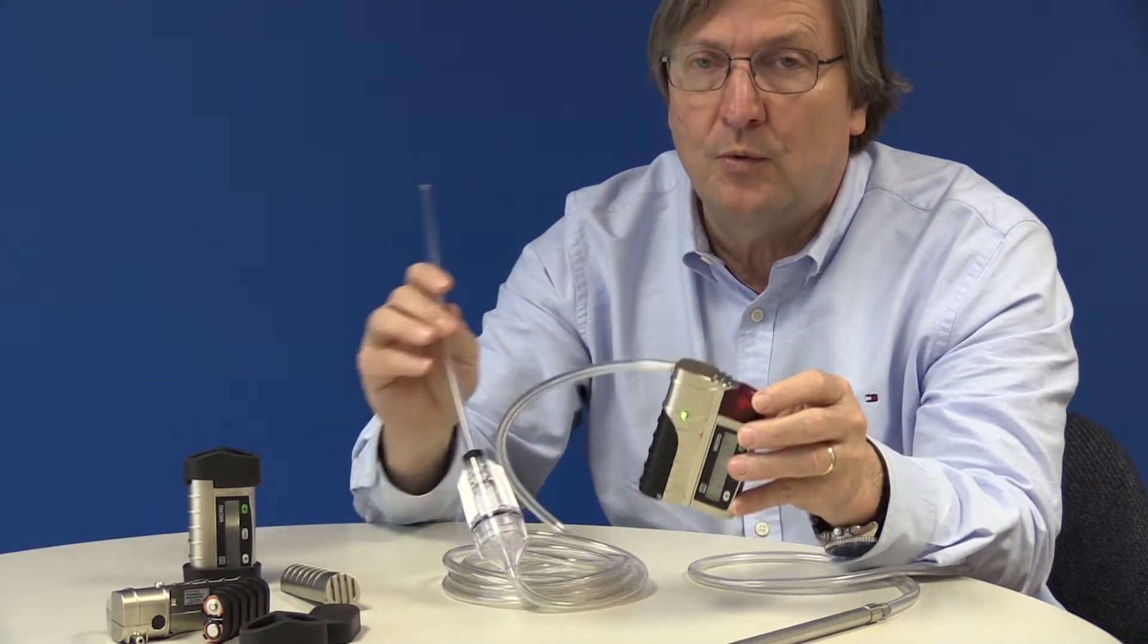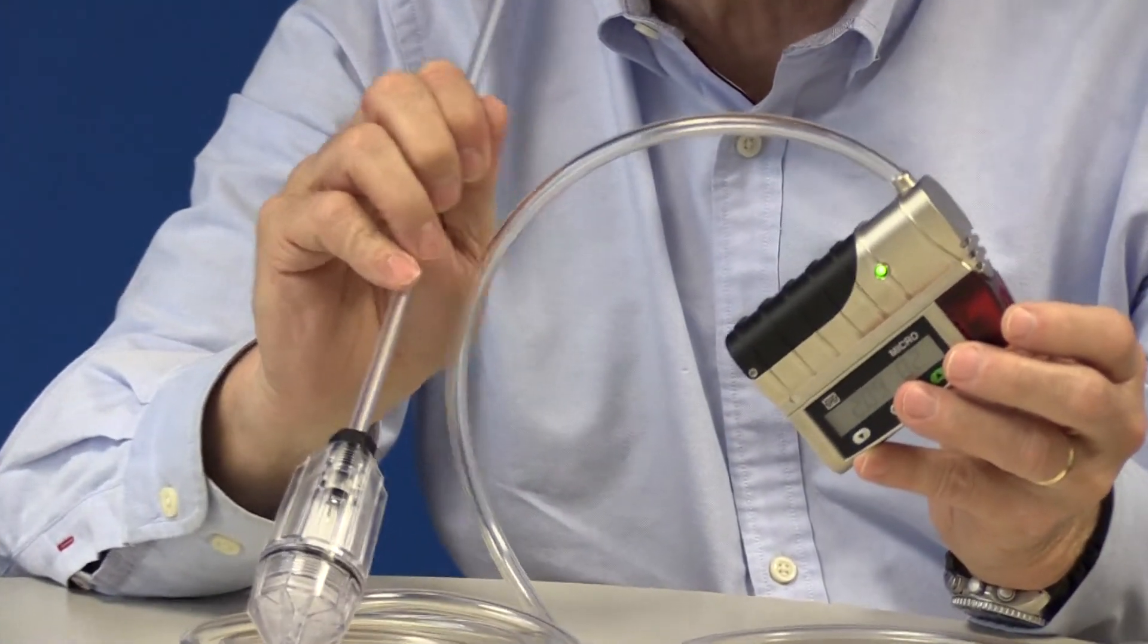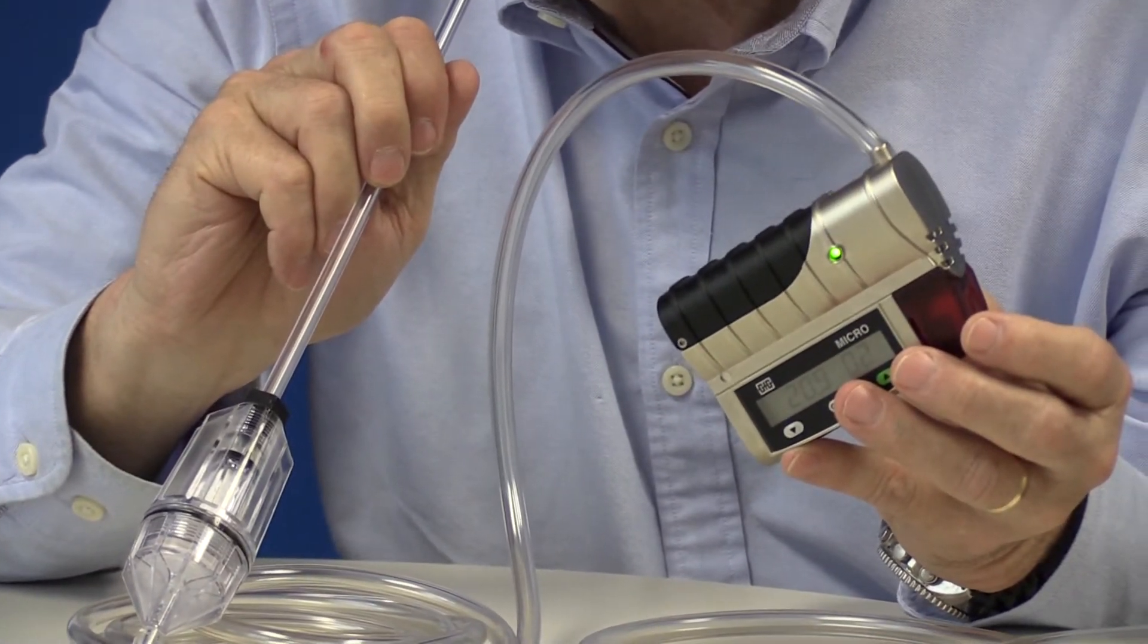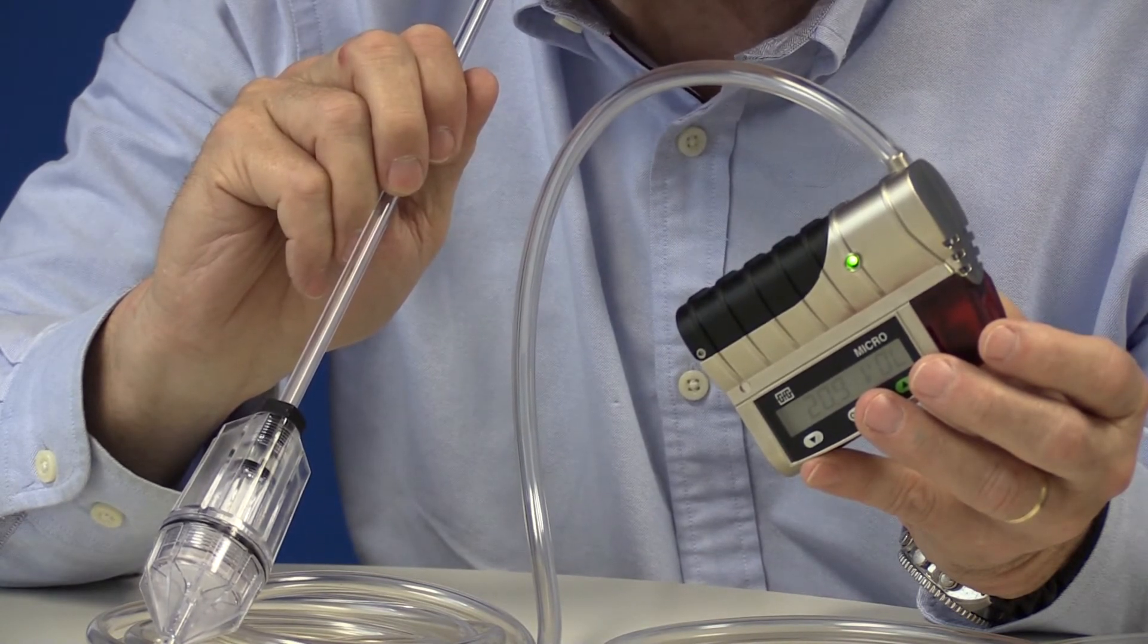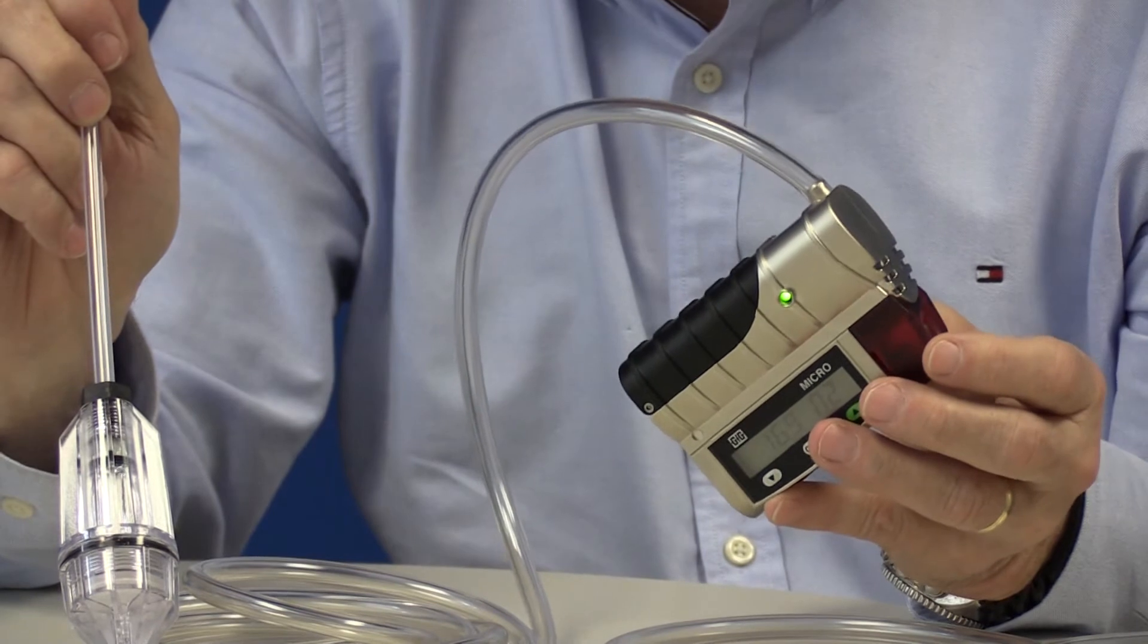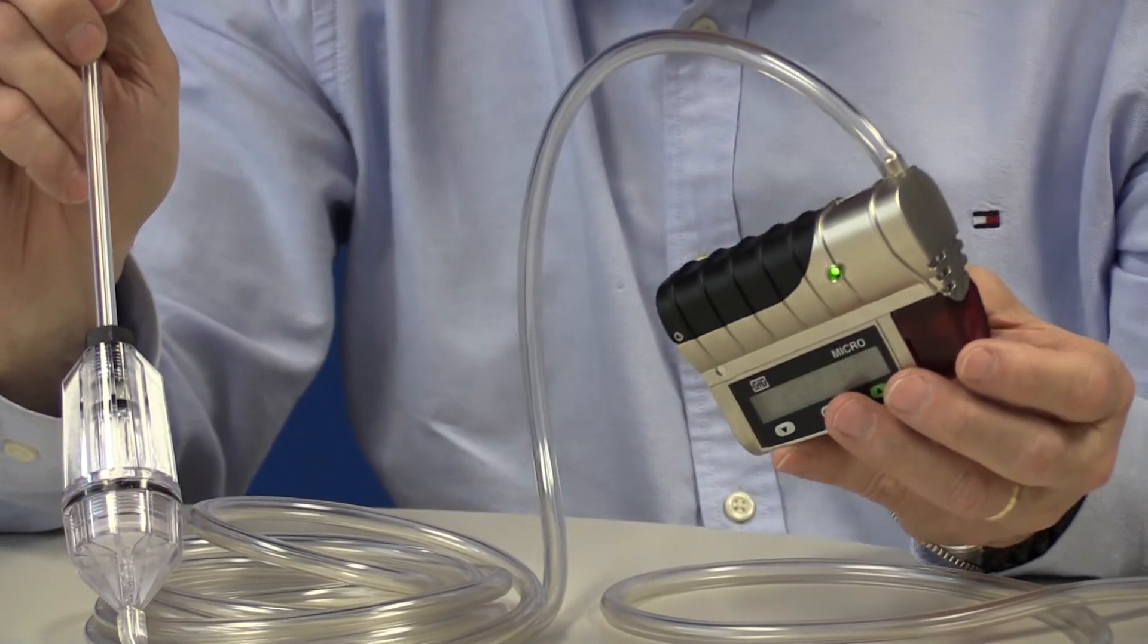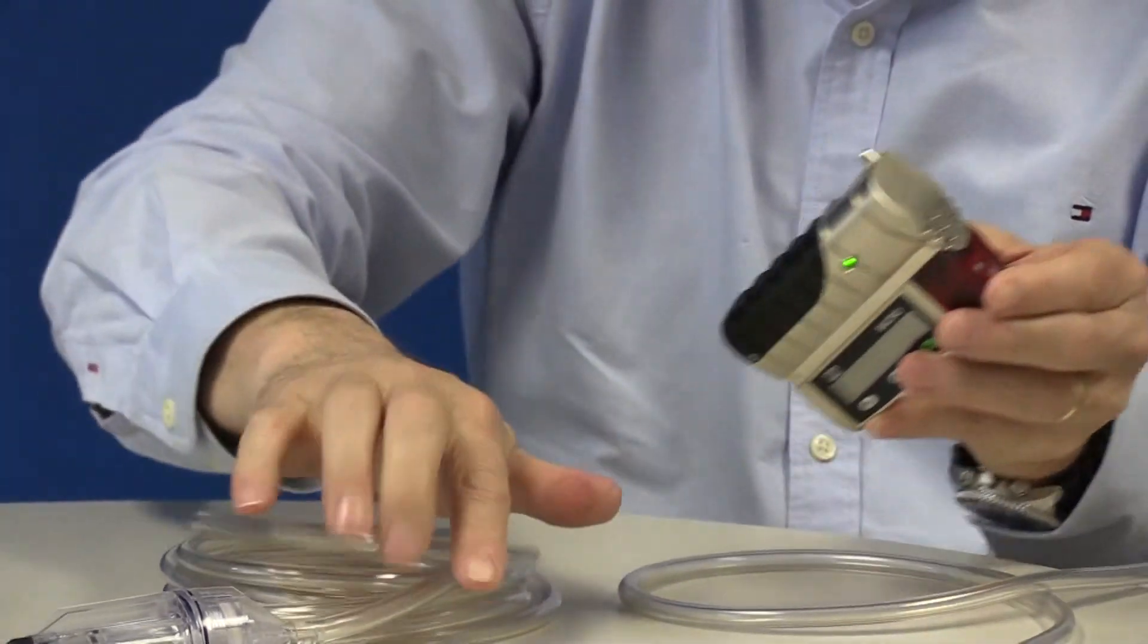So you can see that when I breathe into the end of the tube it will cause an oxygen deficiency. And note the amount of time it takes to move from my mouth to the instrument. So always make sure to give the instrument and pump enough time before you take action on the reading. You want to make sure that you're obtaining a sample from the location that you mean to monitor.